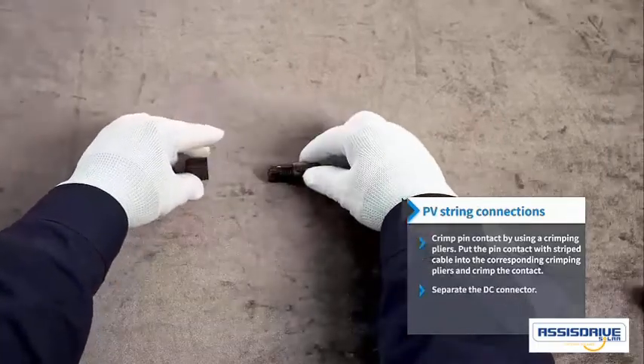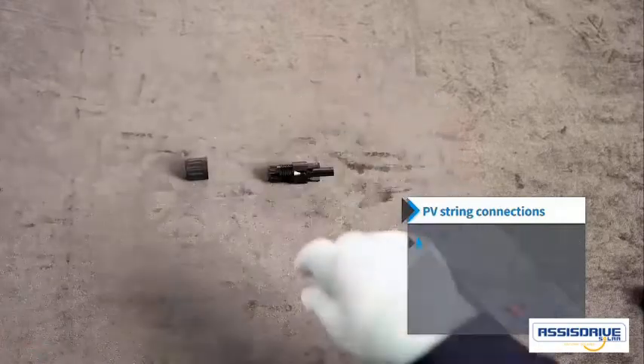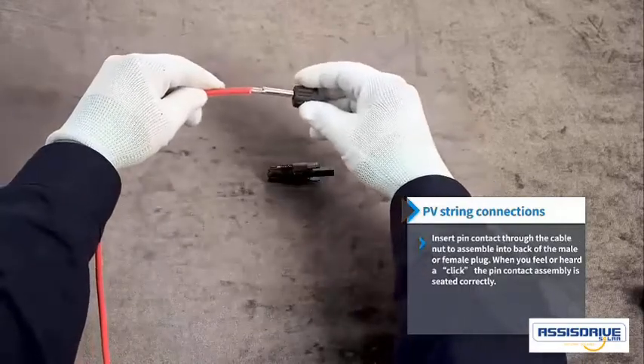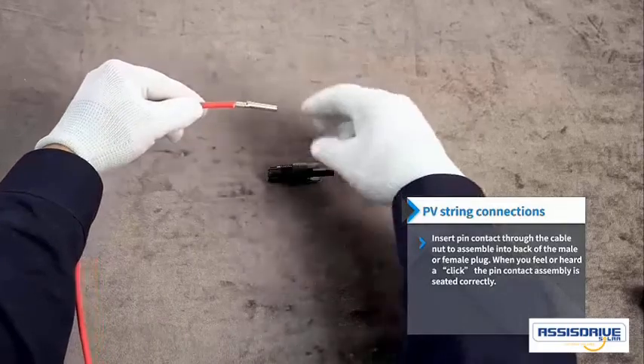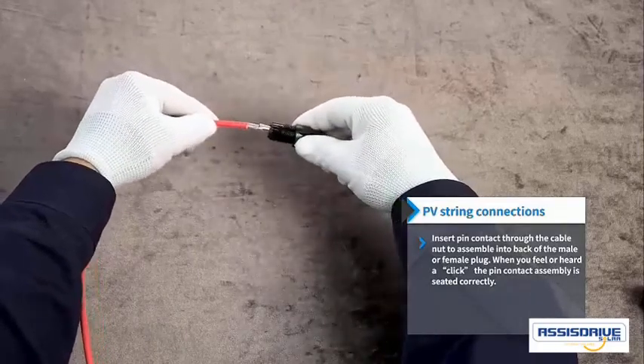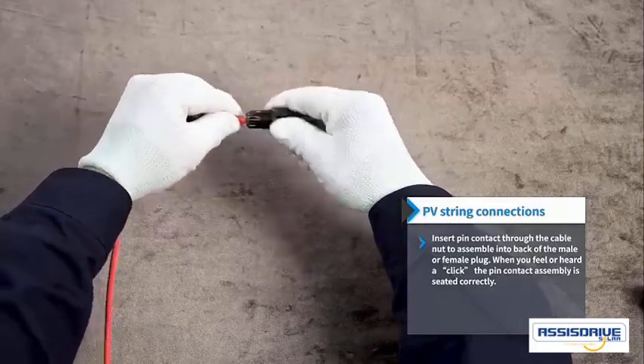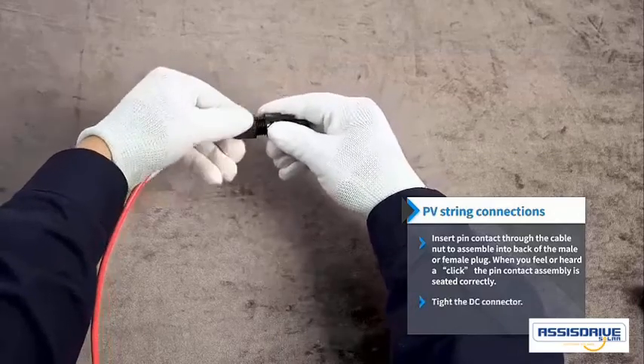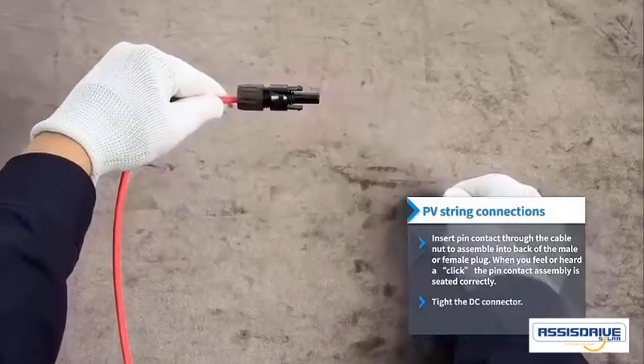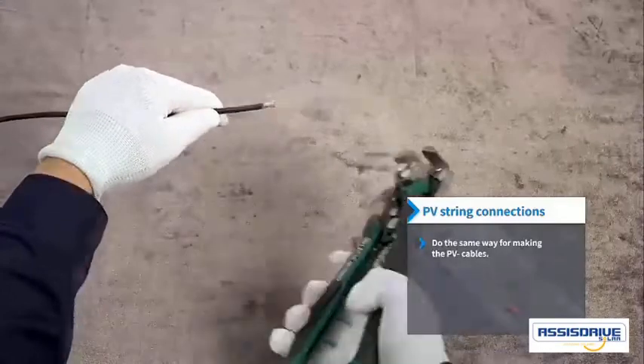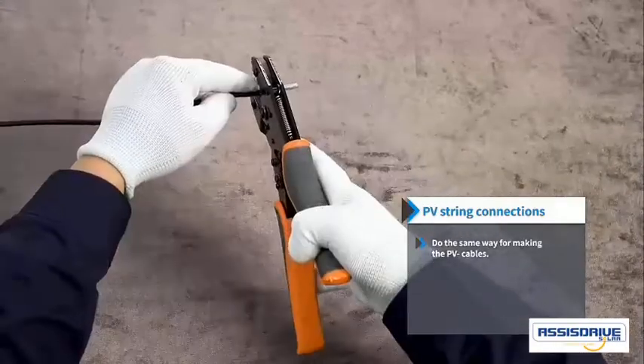Separate the DC connector. Insert pin contact through the cable nut to assemble into back of the male-female plug. When you feel or hear a click, the pin contact assembly is seated correctly. Tighten the DC connector. Do the same way for making the PV negative cables.